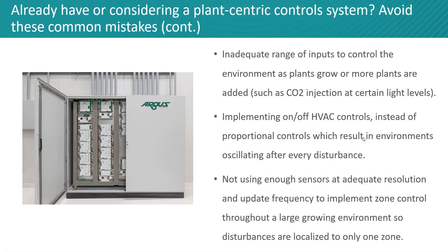We've gone through an exercise where we eliminated those ramping restrictions and dead bands in the HVAC solution, and we were able to double the temperature accuracy through that process. So if you're in a situation where you're not getting what you want, it's quite often buried inside something that isn't tracking where it needs to.